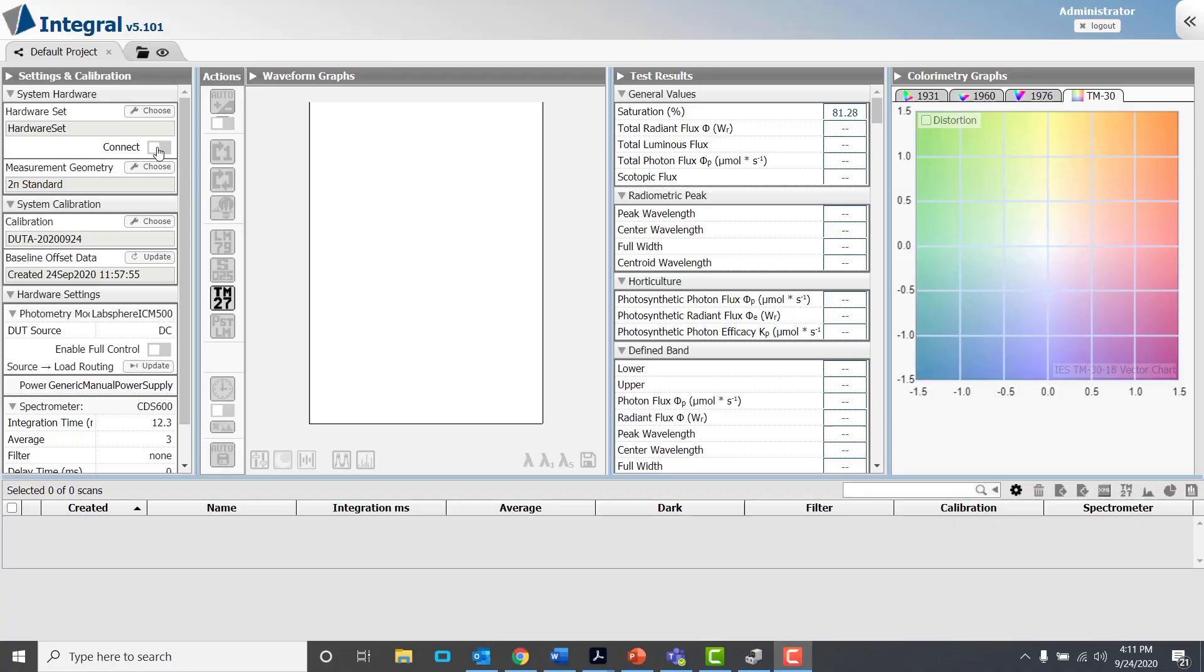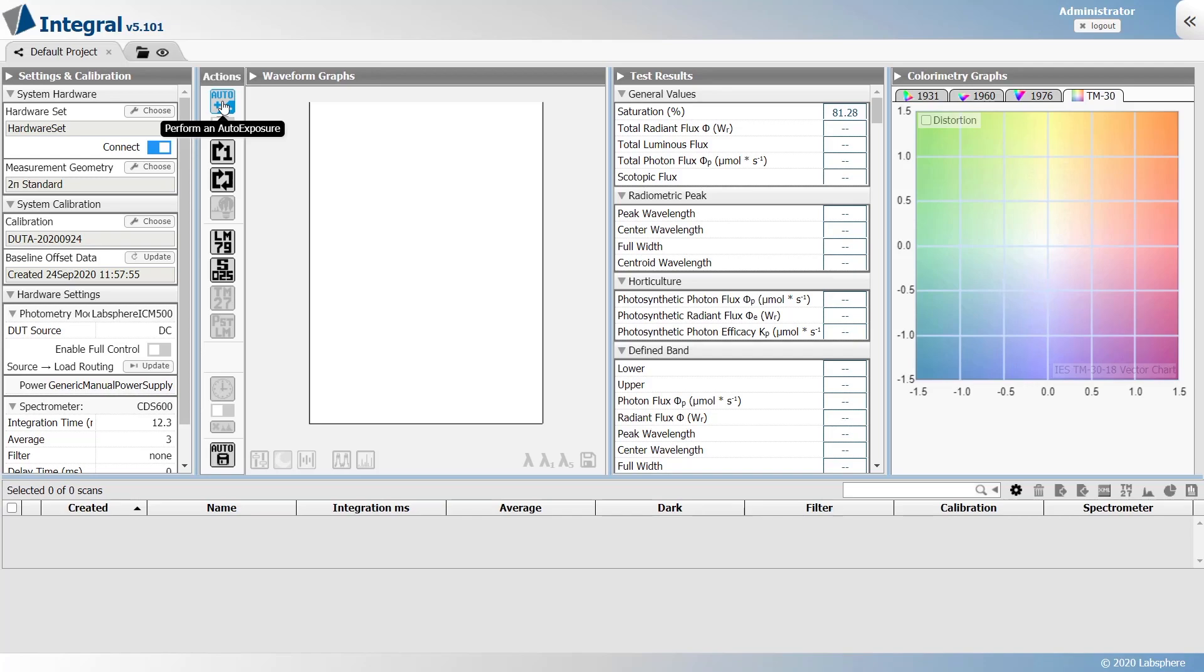Connect the hardware set. Confirm that the calibration is correct for the DUT. With your DUT in the sphere powered on and warmed up, click Auto Exposure, then click Perform Single Scan.